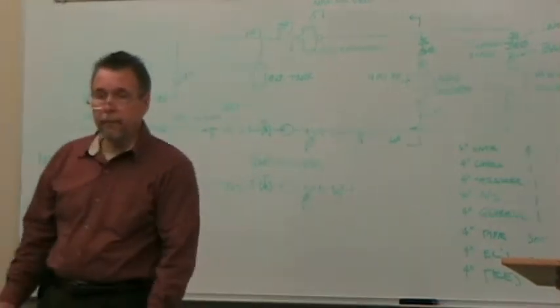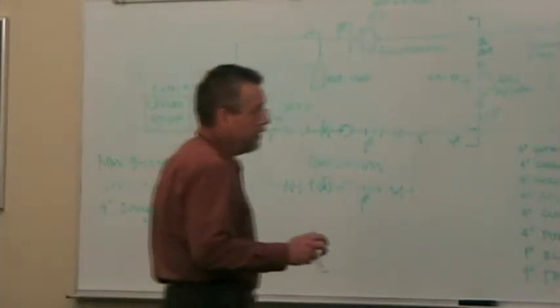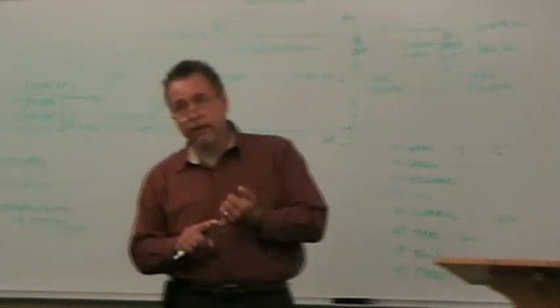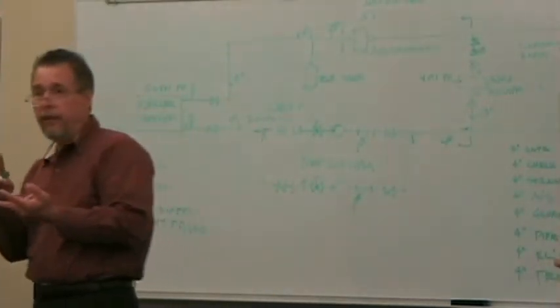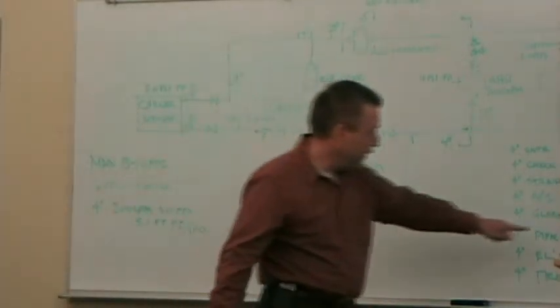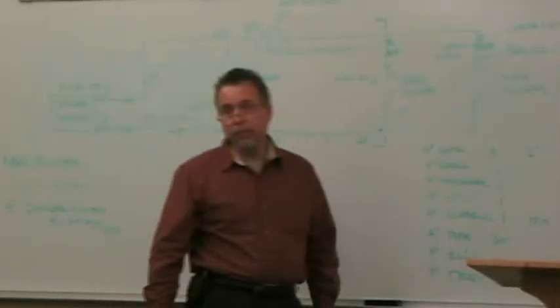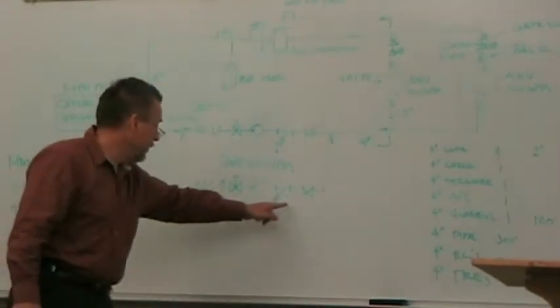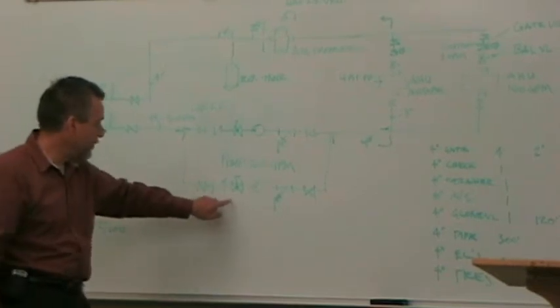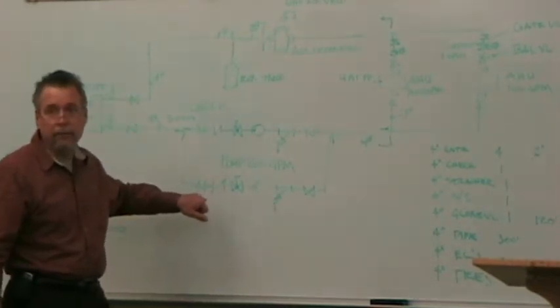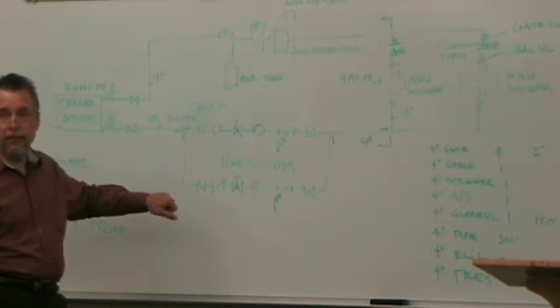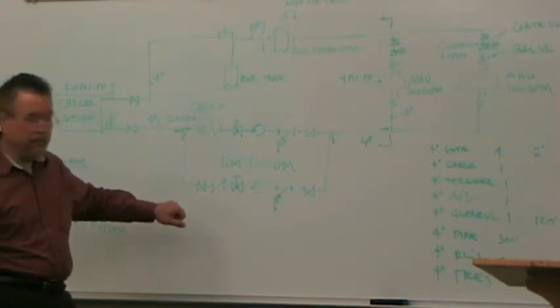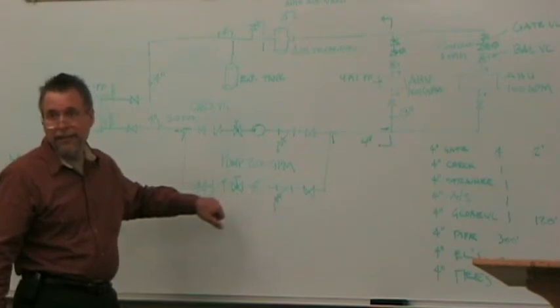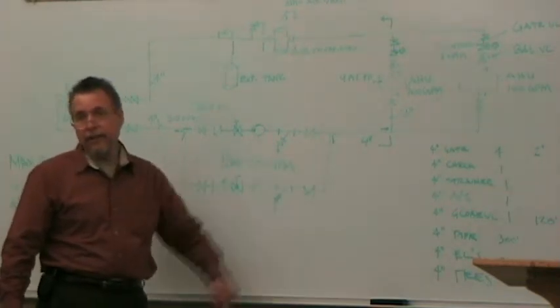What does a triple duty valve do? A triple duty valve is a combination strainer, balancing valve, and check valve. And it has an even higher pressure drop than a globe valve. But once you combine the strainer, the check valve and the balancing valve, it's these three valves in one valve. Some people actually use it as the shutoff valve. That's a mistake, because how do I work on it if I don't put a valve in front of it?